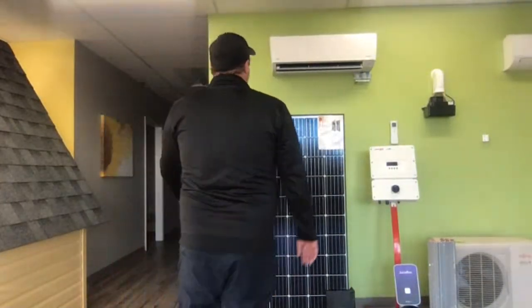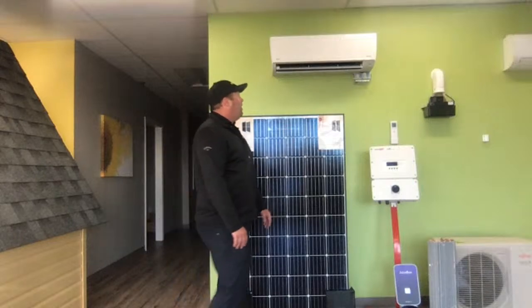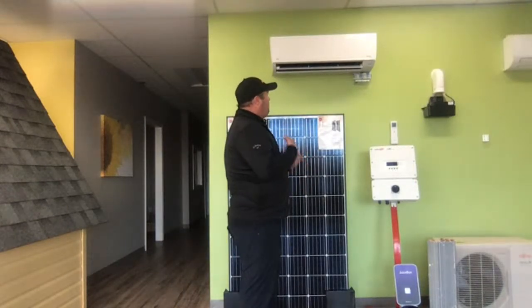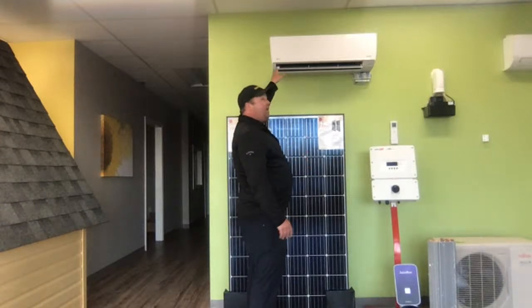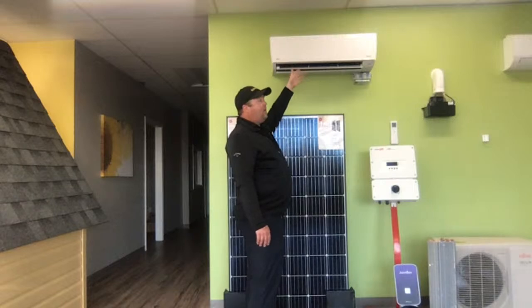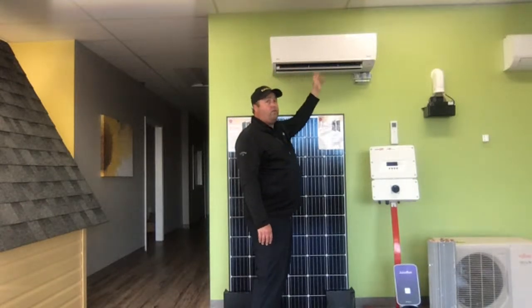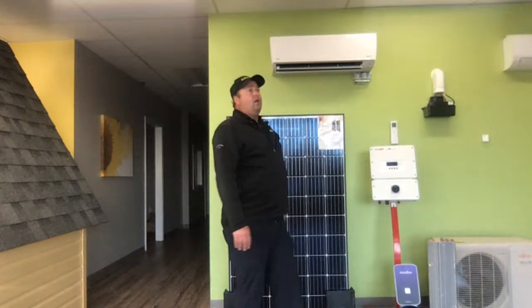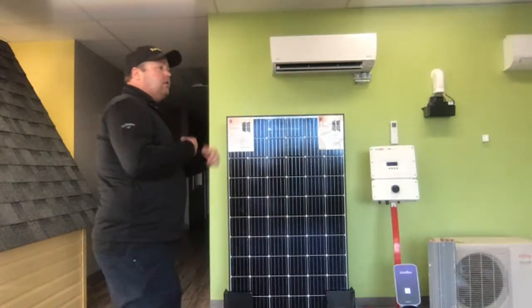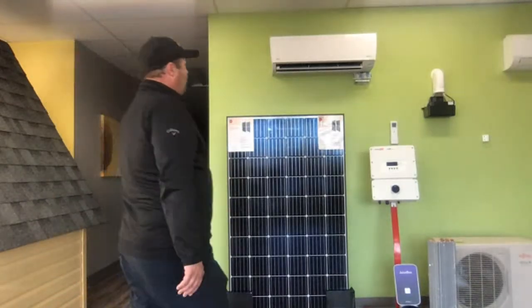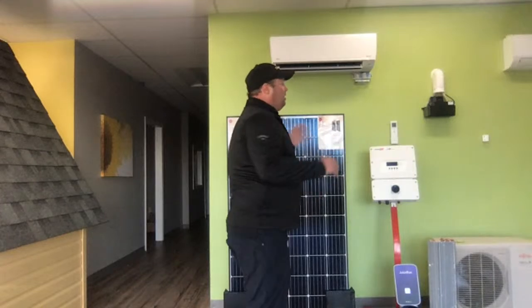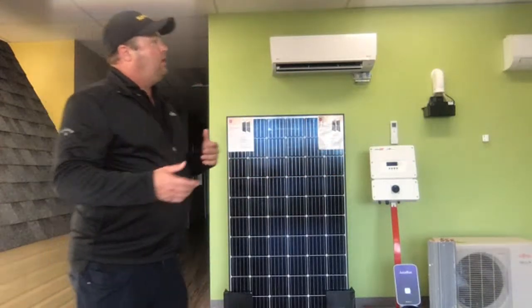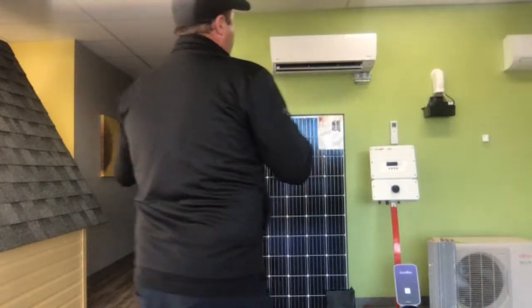Noisy fan, 2 years old—what could it be? It could be a fan motor on its way out. It might not be the greatest heat pump. Or, if you haven't had it cleaned, dirt builds up inside and eventually spreads over to the fan wheel, clogging it up. Then you'll burn out your motor, or get a grind or a tick. Any of these things can happen over time. That goes back to proper maintenance—you don't buy a car and skip the oil changes. Get the oil changed and the car lasts a long time. Skip it, and you might get 20,000 kilometers before the engine blows.